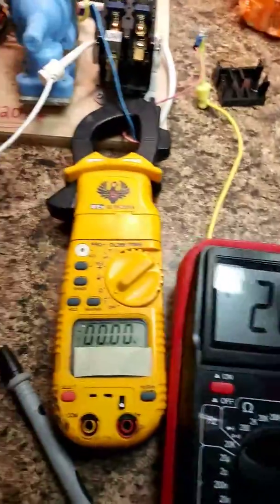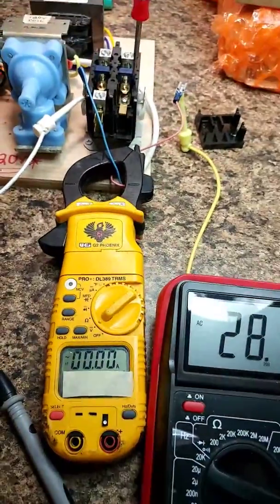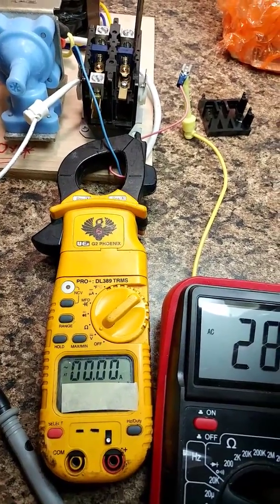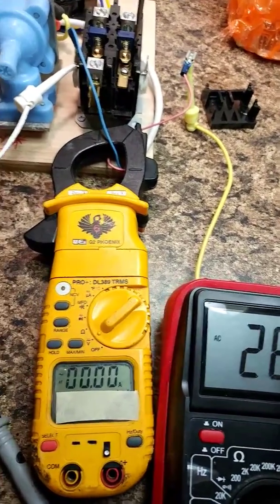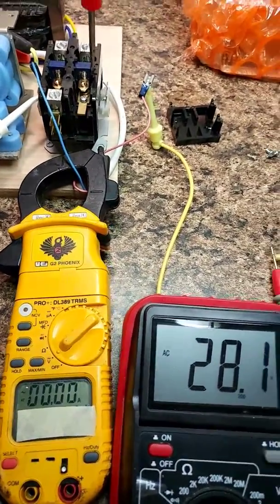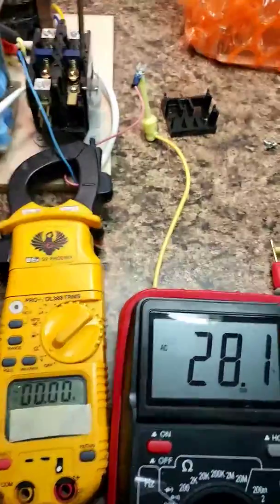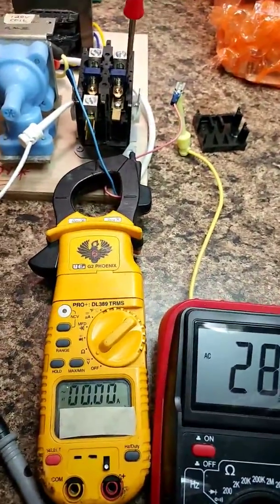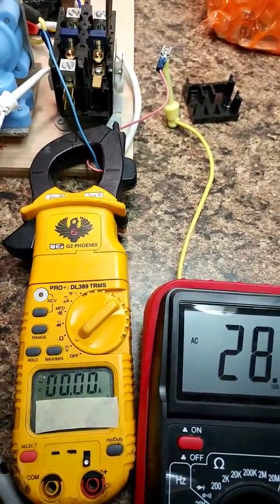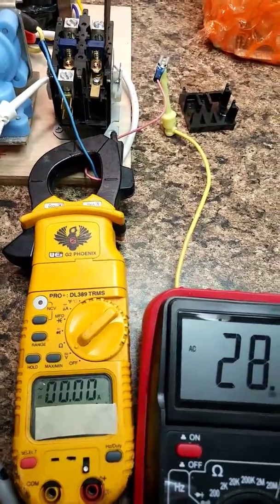So I just wanted to point that out to you. I've seen this happen with small fan relays. I've seen it happen with different relays and different contactors. So just be aware of that. If you've got a situation where you've got a transformer that's blowing or a fuse that's blowing and you're not sure what it is, what I always recommend is isolate everything.